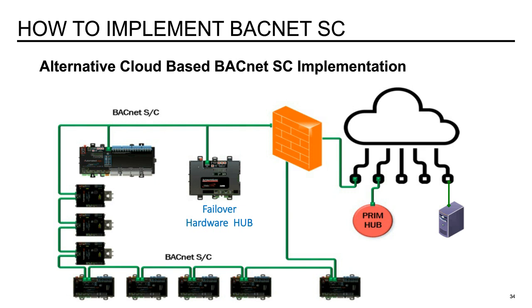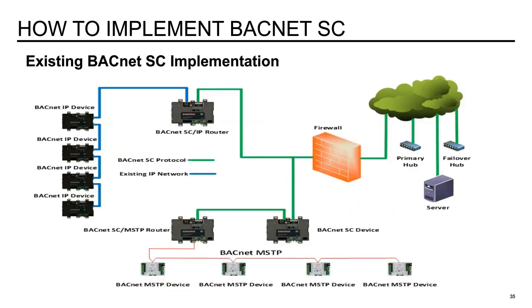Here is an existing BACnet SC implementation. So what I want to point to here is on the left, if you'll notice, there is blue with BACnet IP devices. So if you have existing BACnet IP devices sitting on an IP network, a BACnet SC to IP router is installed. So BACnet IP is talking from the devices that are on the left to the BACnet SC IP router that's at the top. And then the BACnet IP router is talking the BACnet SC protocol, which is in green, through the firewall to the primary hub in the cloud and then the servers in the cloud.